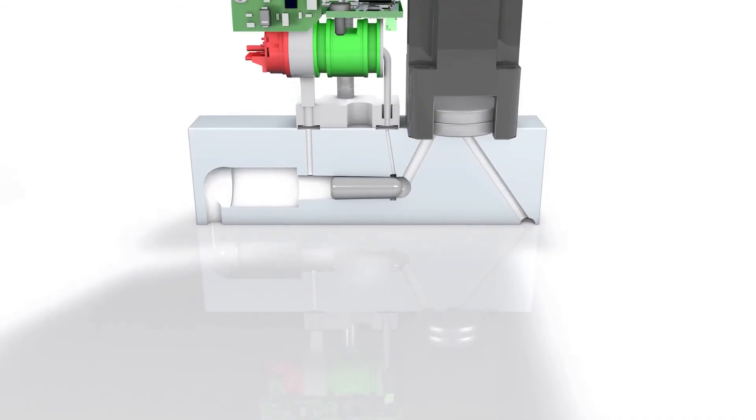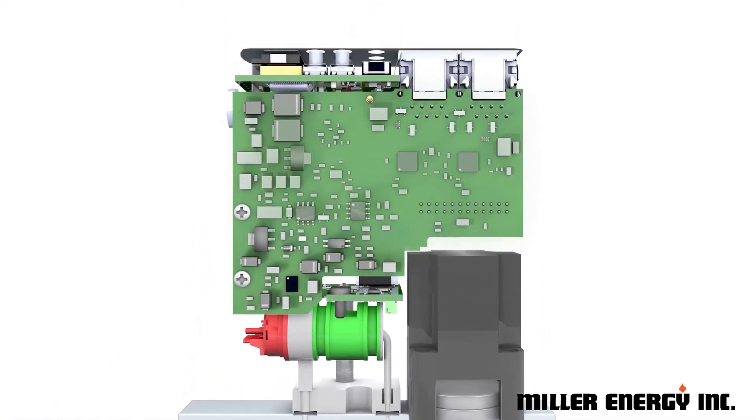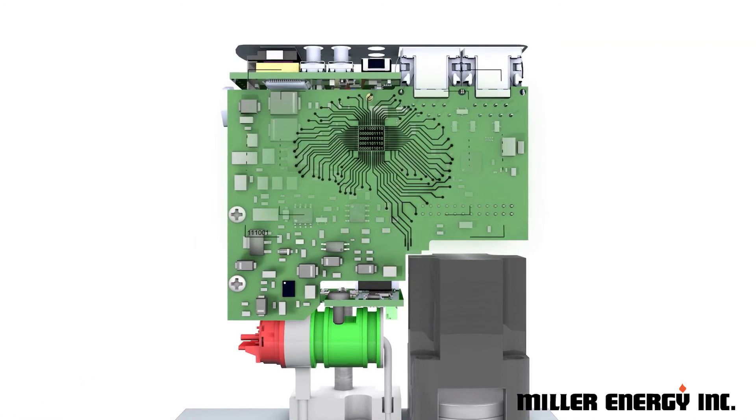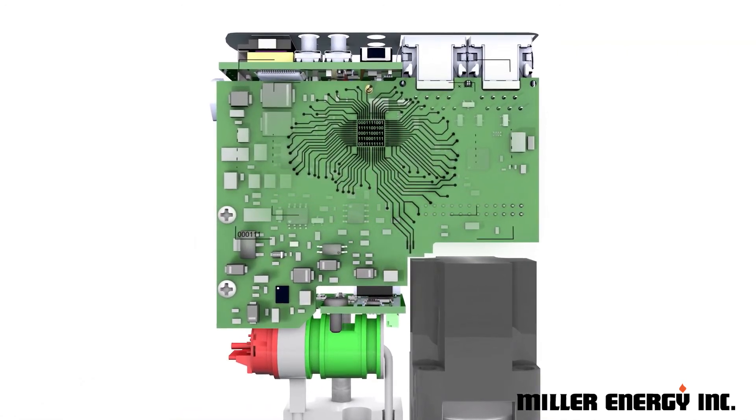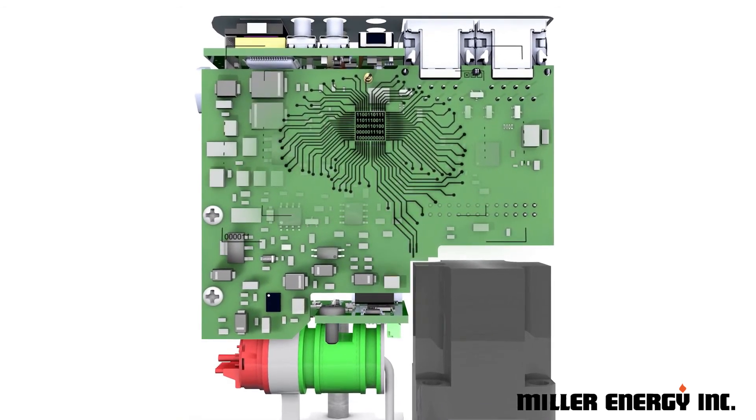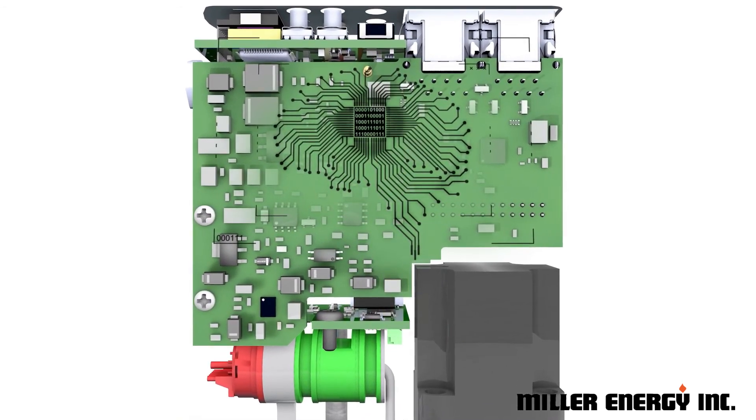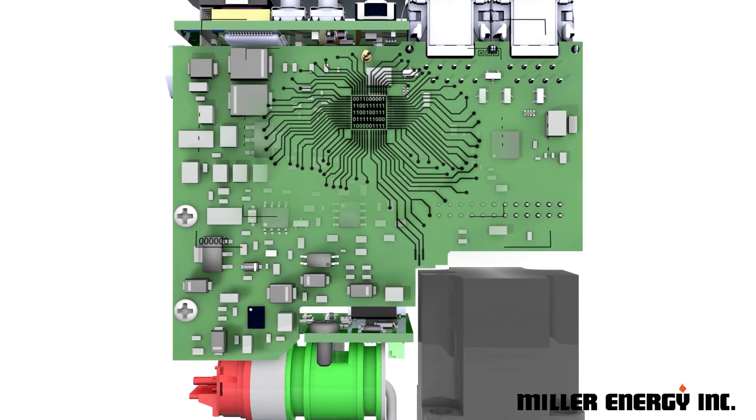Fluid properties are updated for temperature and pressure changes every 2 milliseconds to ensure process gas accuracy under real-world application conditions. This is accomplished by embedding the dynamic gas model in the GP200 device, where the governing fluid mechanics equations are solved in real-time at every signal processing cycle.